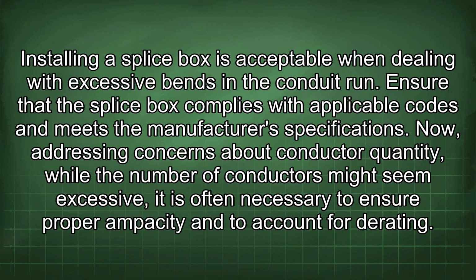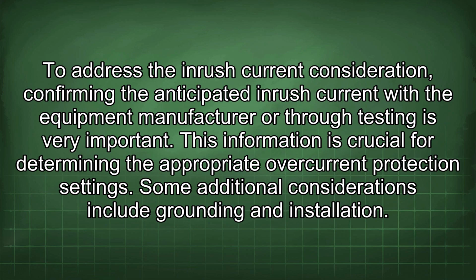Installing a splice box is acceptable when dealing with excessive bends in a conduit run. Ensure that the splice box complies with applicable codes and meets the manufacturer's specifications. Now, addressing concerns about conductor quantity. While the number of conductors might seem excessive, it is often necessary to ensure proper ampacity and to account for derating. To address the inrush current consideration, confirming the anticipated inrush current with the equipment manufacturer or through testing is very important. This information is crucial for determining the appropriate overcurrent protection settings.